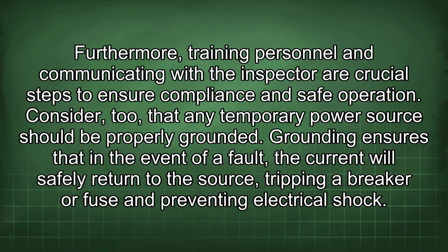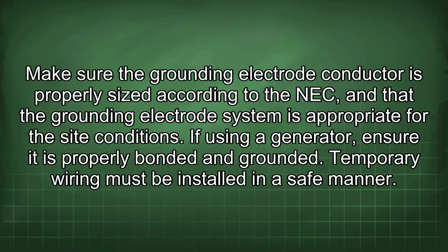Consider, too, that any temporary power source should be properly grounded. Grounding ensures that in the event of a fault, the current will safely return to the source, tripping a breaker or fuse and preventing electrical shock. Make sure the grounding electrode conductor is properly sized according to the NEC and that the grounding electrode system is appropriate for the site conditions.